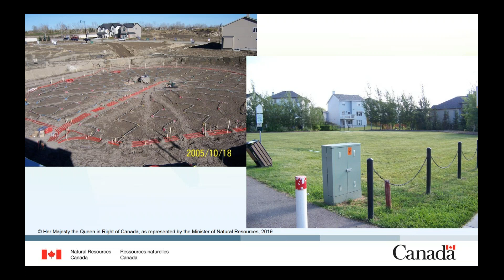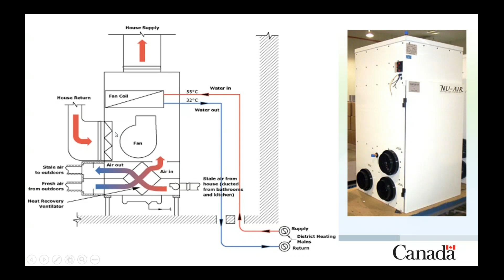The system was designed based on building simulations, and we had help from our buildings colleagues to design and evaluate the heat load for those houses. The houses had a higher level of efficiency than the houses that were typically built in that area at that time. And the system was then simulated in TRNSYS to optimize the design and evaluate the parameters of design and operation. Since the beginning, it has been monitored. So Drake Landing has been operational now for 12 years, and we have 12 years of fairly extensive data on its operation.